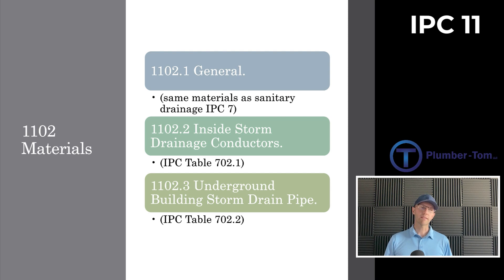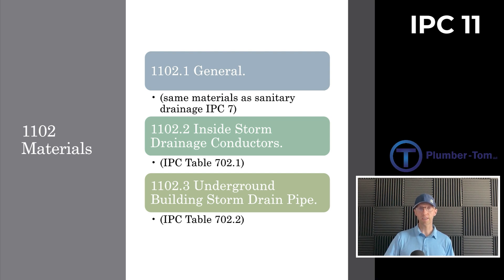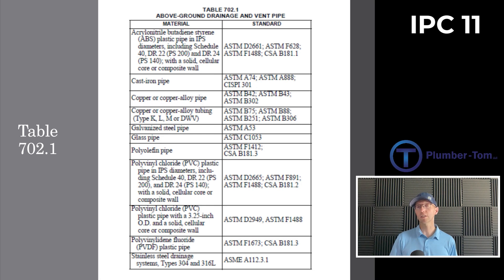In 1102, we get specifics about the materials used for storm drains. 1102.1 says in general it's going to be the same materials as the sanitary drainage system from Chapter 7. 1102.2 says inside storm drainage conductors are listed on Table 702.1, and underground building storm drain pipe is listed on Table 702.2. Table 702.1 includes a variety of materials: ABS, cast iron, copper, PVC. The most common on storm drains are cast iron and PVC.